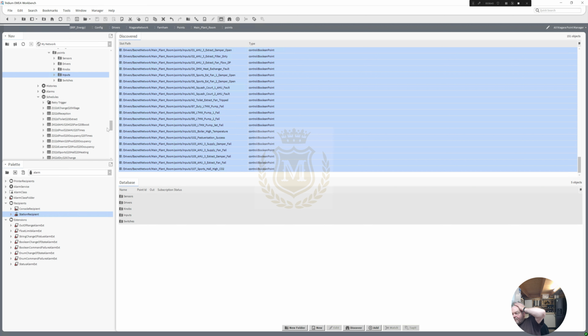That's everything ready for me to go with the graphics now. I've got all my points back to the cloud, and I can actually adjust any points, and they will adjust at the Tridium Niagara station, which of course via BACnet will adjust them in the IQ4s. So the only other thing I've got to do is the schedulers, to then bring the schedulers into the controller to then send to the IQ4s, but that's not a problem.